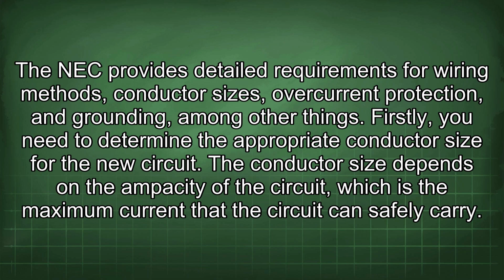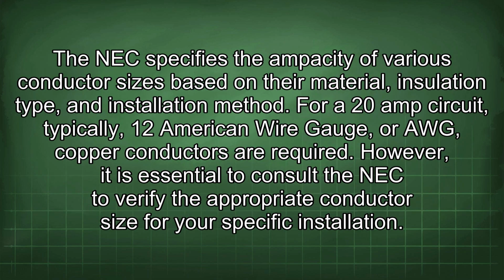Firstly, you need to determine the appropriate conductor size for the new circuit. The conductor size depends on the ampacity of the circuit, which is the maximum current that the circuit can safely carry. The NEC specifies the ampacity of various conductor sizes based on their material, insulation type, and installation method. For a 20 amp circuit, typically 12 American wire gauge, or AWG, copper conductors are required. However, it is essential to consult the NEC to verify the appropriate conductor size for your specific installation.